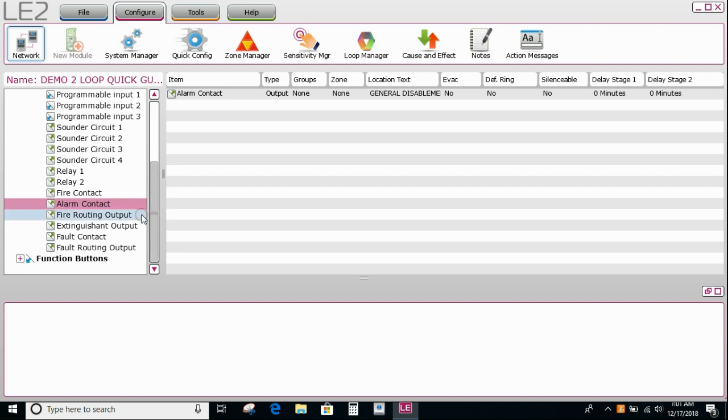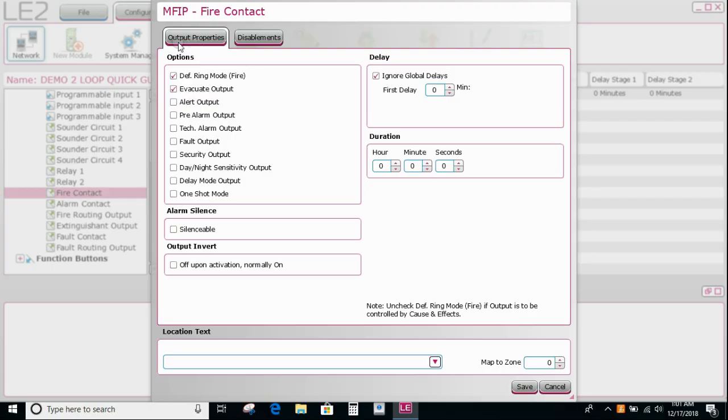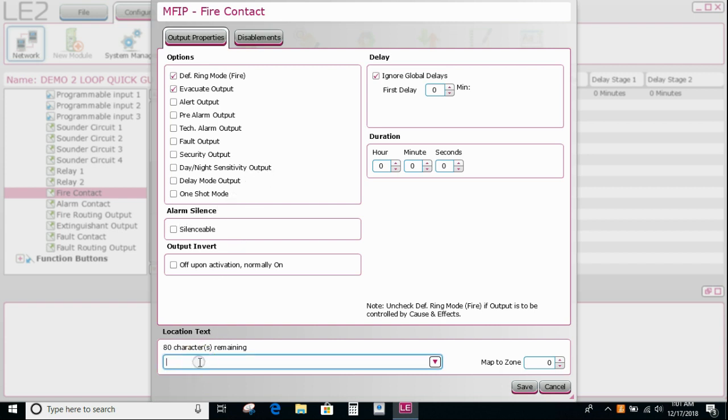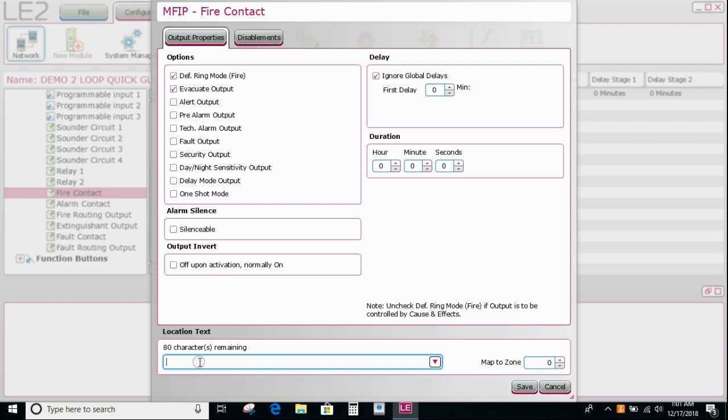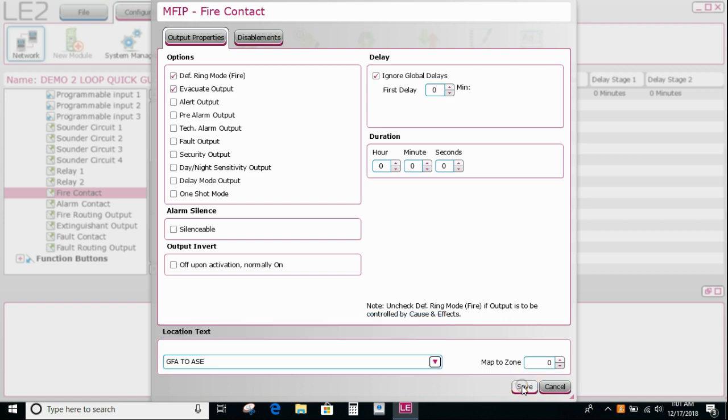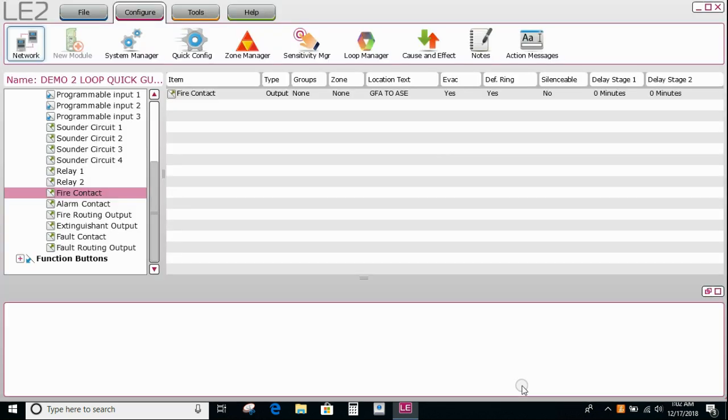Now our fire contact is typically the one that's going to the brigade. If I double check, it's been set up as default ring mode and it's not silenceable. So effectively when we silence the panel on the front, it will not reset until we press the reset button. GFA to ASE typically, and then say save.